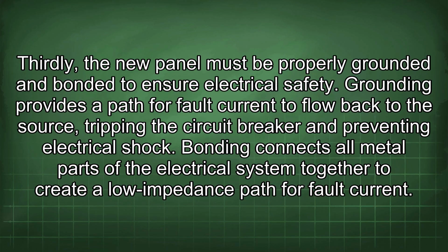Thirdly, the new panel must be properly grounded and bonded to ensure electrical safety. Grounding provides a path for fault current to flow back to the source, tripping the circuit breaker and preventing electrical shock. Bonding connects all metal parts of the electrical system together to create a low impedance path for fault current.